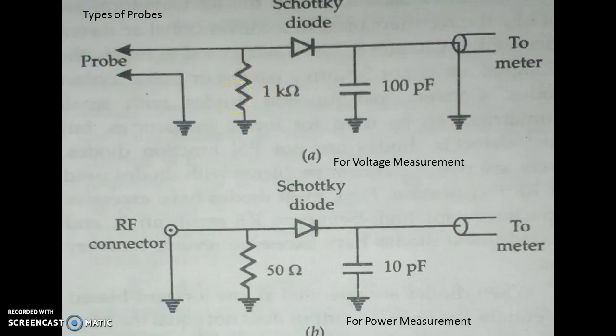This is one way of measuring voltage and power; the power measurement can be made in the range of nanowatts. Besides this, there are other methods of measuring power. Absorption power meters are the most commonly used. In these absorption-type power meters, there is a component that absorbs power and measurements are made based on the power absorbed by this element.